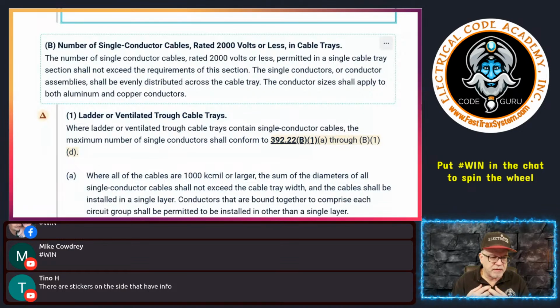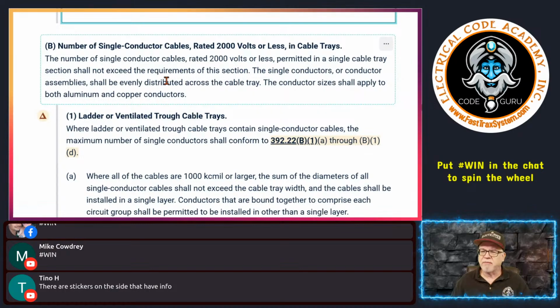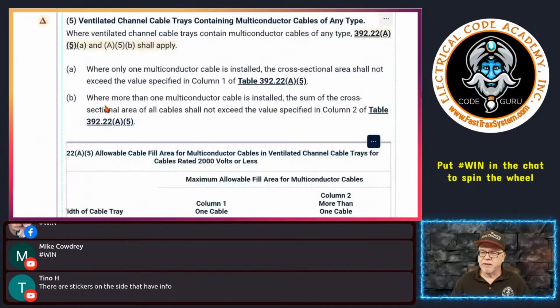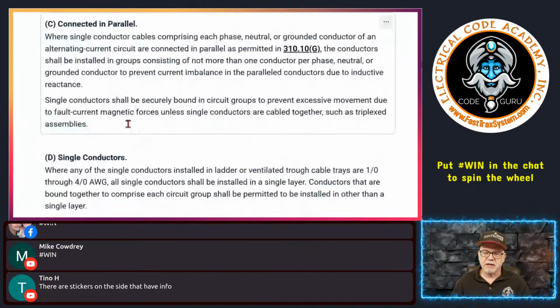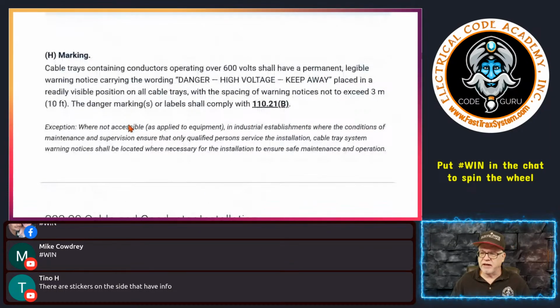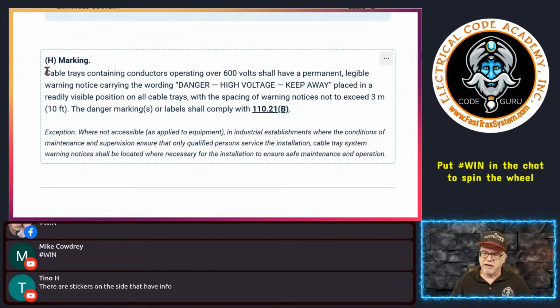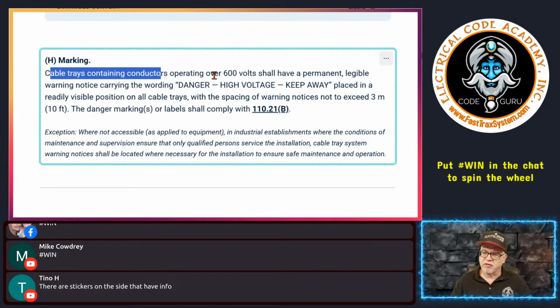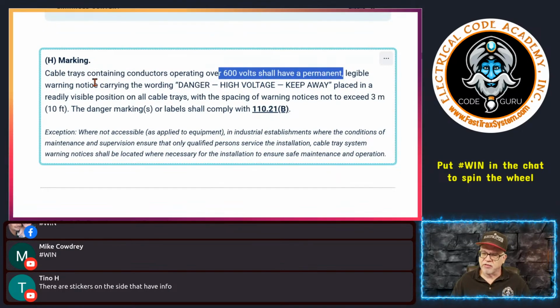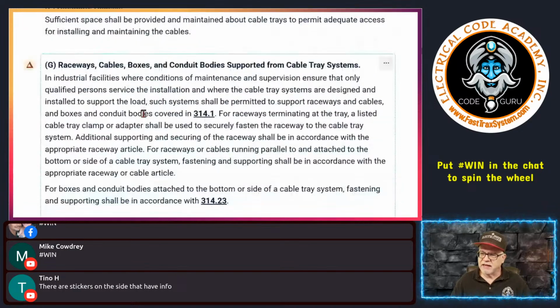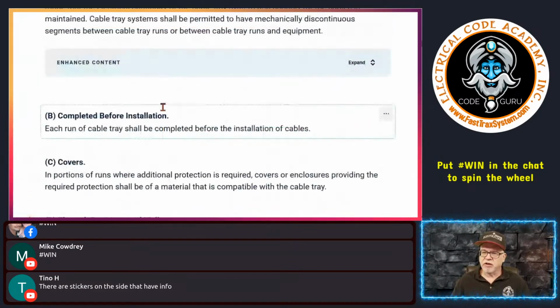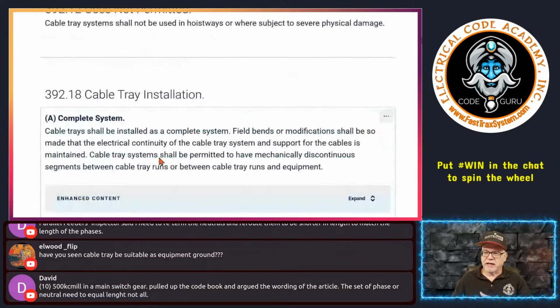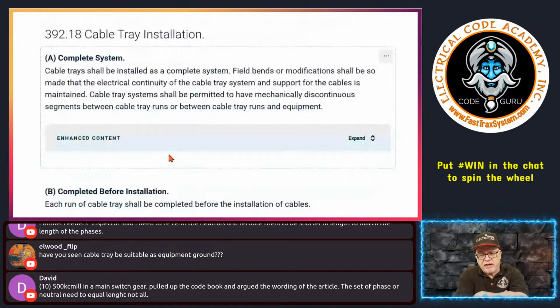There are stickers typically on the side of a cable tray. They usually will have markings on the side of them, depending on what they're used for. If they're going to have service conductors in there, and there you go. So here's your markings that you're talking about here. Cable trays containing conductors over 600 volts, then here's some markings that you have to have, that type of thing. So typically you're going to have all types of markings on the side of it. If service conductors are in there, then there are requirements to have it say that there are service conductors in there, obviously. Okay.